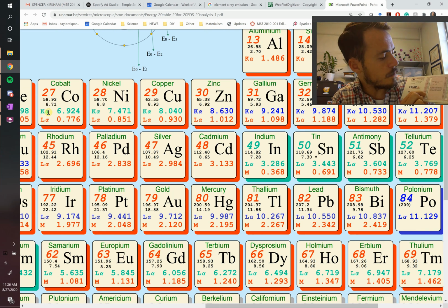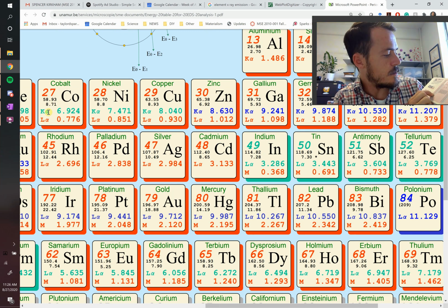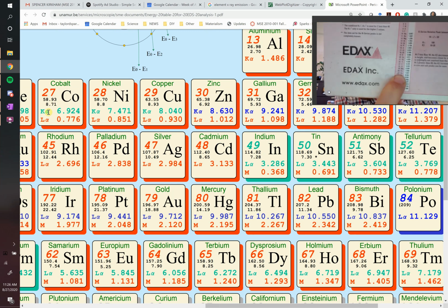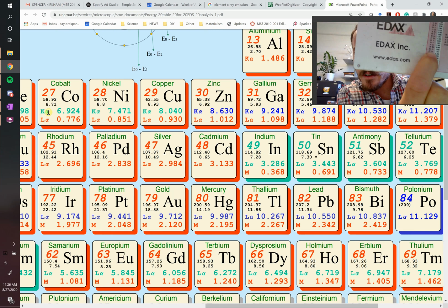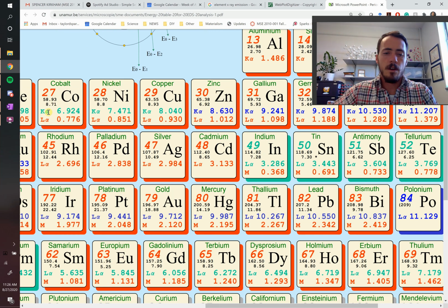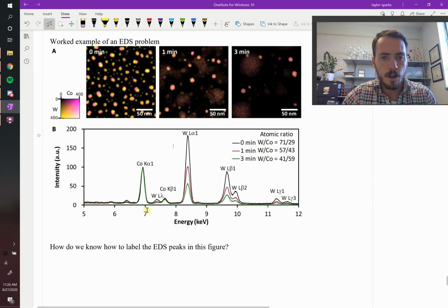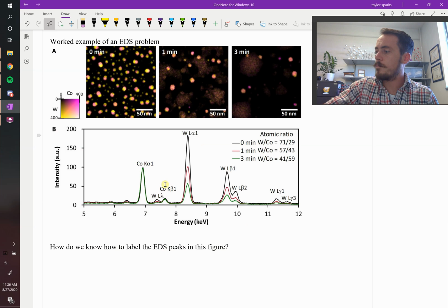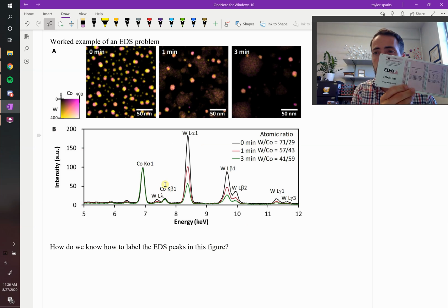And then I look for cobalt. Cobalt right there says 7.64. Sorry, that's hard to read, but it says 7.64. And sure enough, in this plot, right here between 7 and 8, you've got 7.64, and there's the cobalt K beta 1. So you know for sure that it's cobalt and not erbium. To make sure, you'd want to check the erbium also. It doesn't have a peak there.